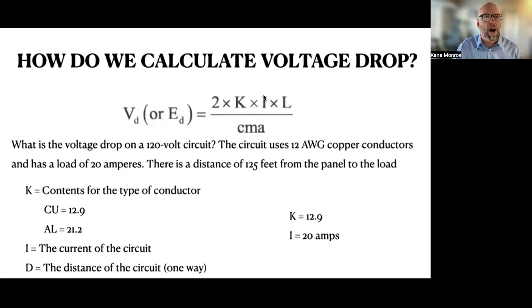Next, we got to figure out I. I is current. And right there, it tells you right there, the load of 20 amperes was used in this question. So I is 20. Next, we have to find the distance. The distance is 125 feet. They told us there. So K-I-D or K-I-L. There's all your information you need there. Only thing we're missing is the circular mils.